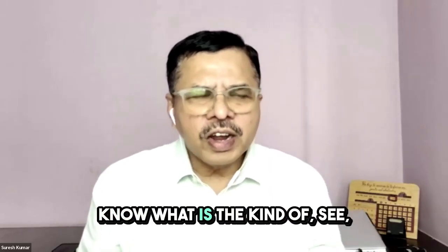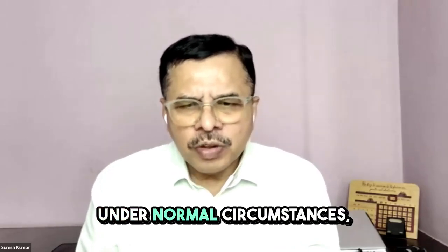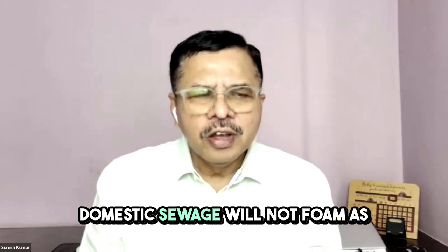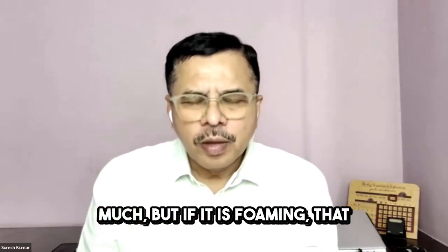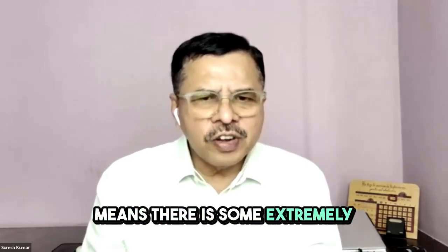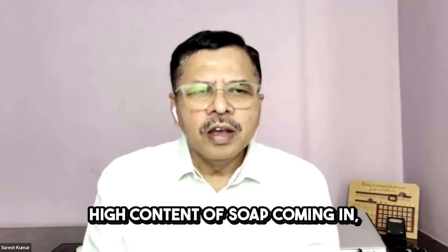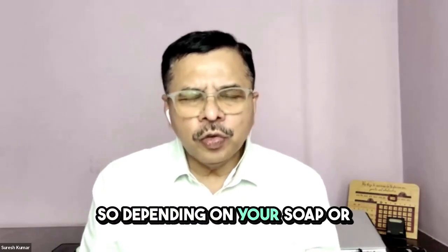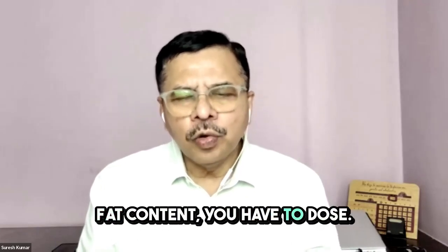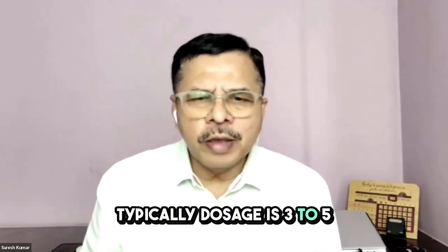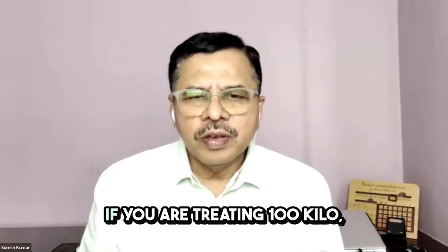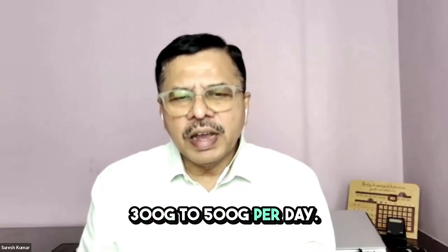Under normal circumstances, domestic sewage will not foam as much. But if it is foaming, that means there is some extremely high content of soap or fat coming in. So depending on your soap or fat content, you have to dose. Typically, the dosage is 3 to 5 ppm, not more than that - that means per kl of water, 3 to 5 grams. If you are treating 100 kl, it's 300 to 500 grams per day.